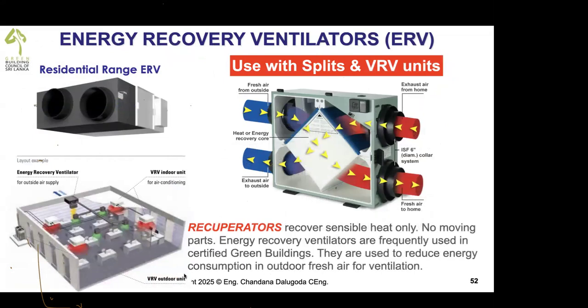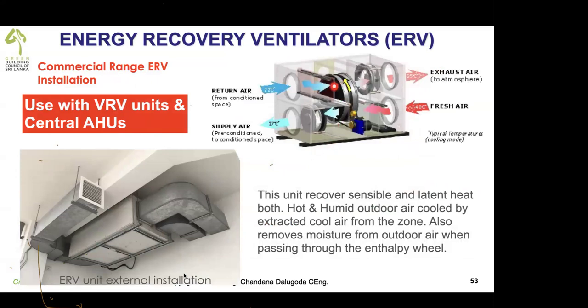And the other thing is energy recovery. We'll have to use energy recovery ventilators to reduce the energy from outdoor air introduction. So outdoor air can be cooled by exhausting cold air from the room. For split units, VRF and split units, we can use a recuperator like this. We'll have to use this kind of an energy recovery ventilator. It extracts 24 degrees C air and cools the incoming 32 degrees. Only sensible cooling. But in larger cases, we can use energy recovery ventilators with an enthalpy wheel. The advantage is it reduces sensible heat and it absorbs water vapor in the air coming from outdoors. So it removes water vapor too.